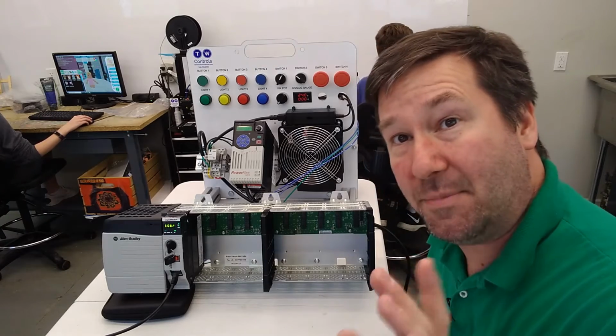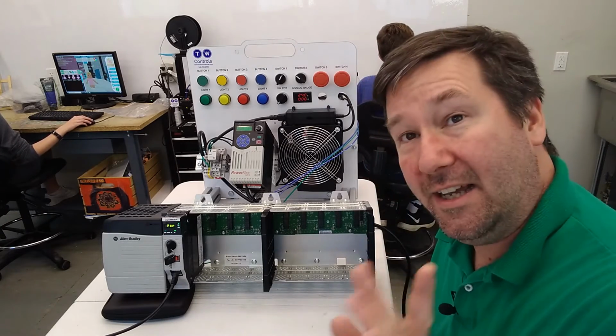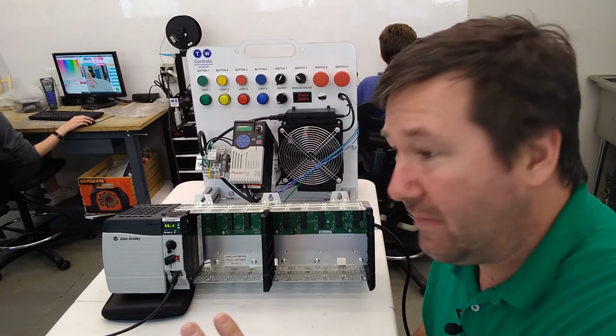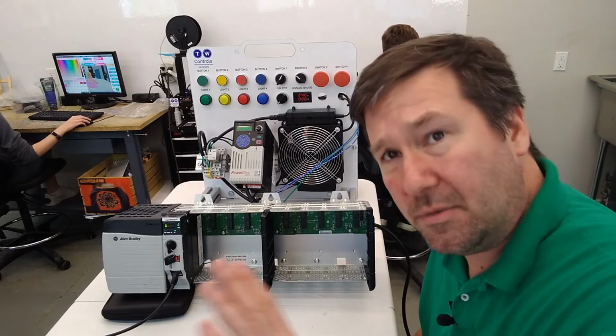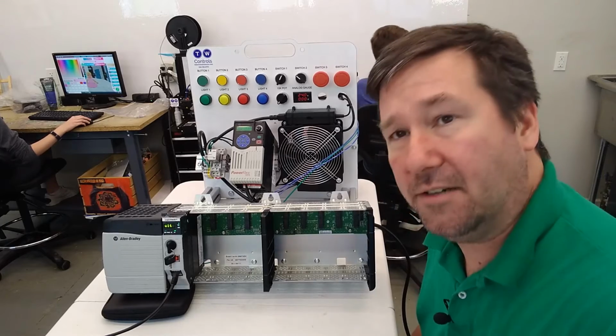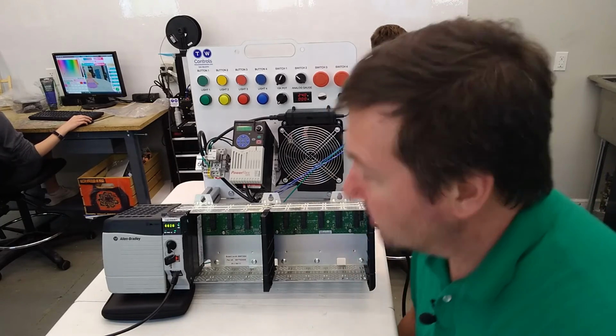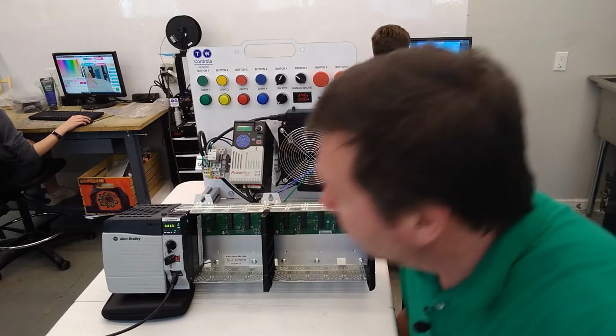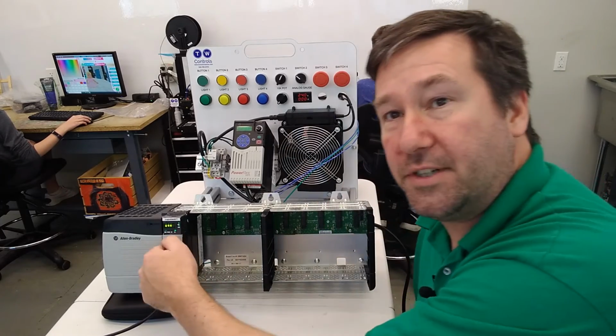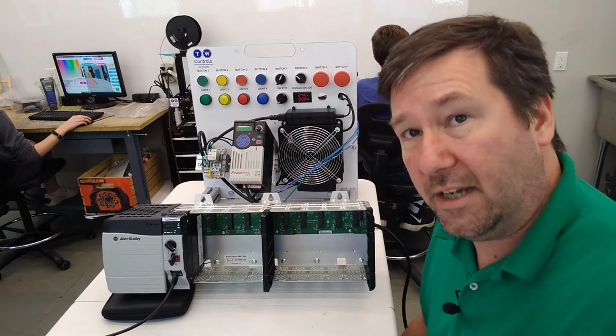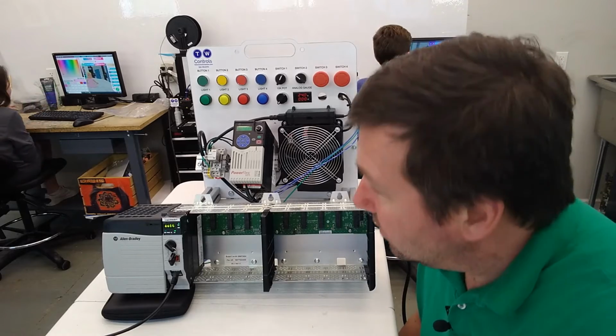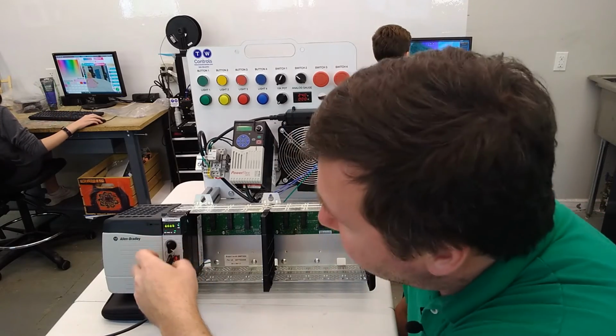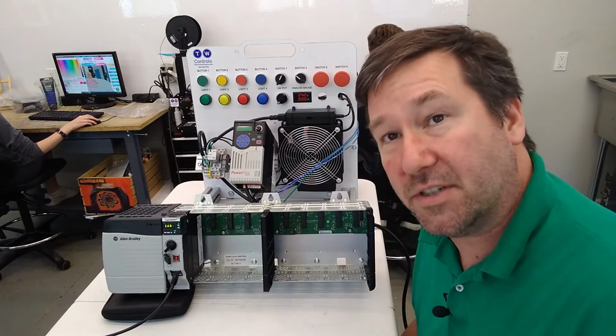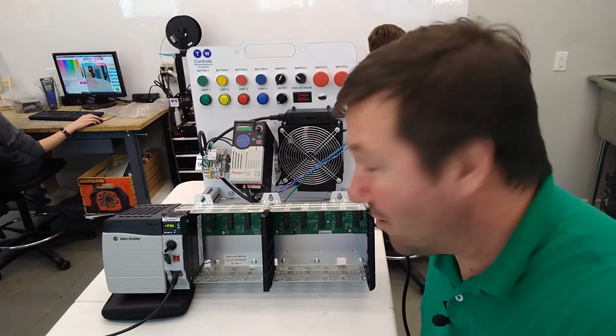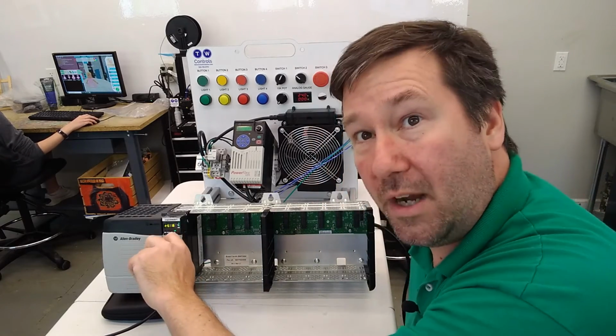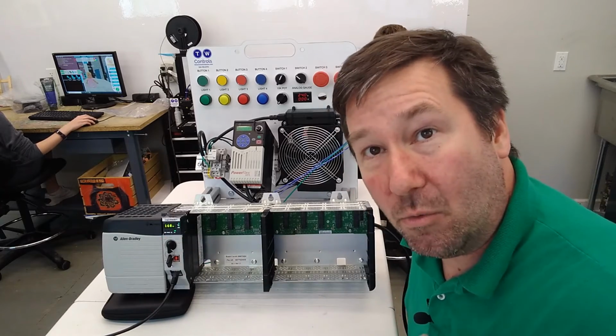And I want to show you something that happens way too often. A machine is down and they can't get it to run. You've got some people working on it, and somebody decides, oh, let's look at this PLC here. They're looking at it, and, oh, well, it's in remote. Let's switch it over to run. Okay, it still isn't working. All right, well, what's this other position doing? They switch it over there. Okay, it still doesn't work. So then they do the right thing and put it back exactly where it was.